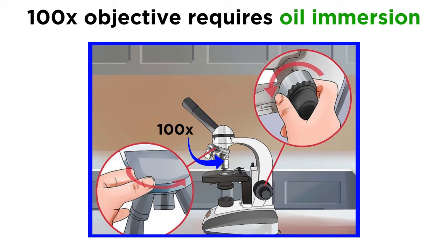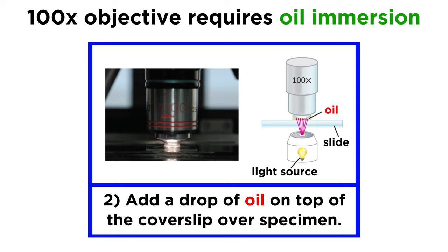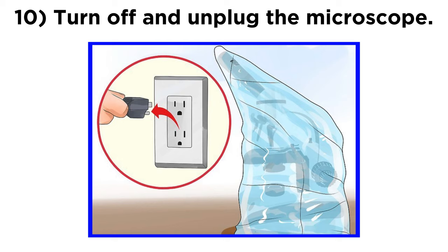It's important that when using the one hundred times objective, it is set up for oil immersion to improve the resolution of the image. To do this, rotate the nosepiece so that the specimen is between the forty and one hundred times objectives, and add a drop of oil on top of the cover slip which sits over the specimen. Then rotate the nosepiece so that the one hundred times objective is submerged in the oil and over the specimen without scraping the lens.